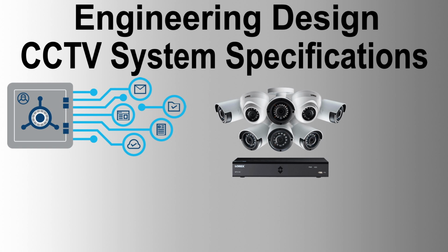CCTV system cabinets. CCTV cabinets shall house system equipment such as FOC patch panels, video encoders, decoders, Ethernet switches, and communication card connectivity to SDH equipment. Cabinets shall be of standard dimensions of 2100 mm H by 800 mm W by 800 mm D, with lockable front and back doors, and of freestanding type with cable entry from the bottom.